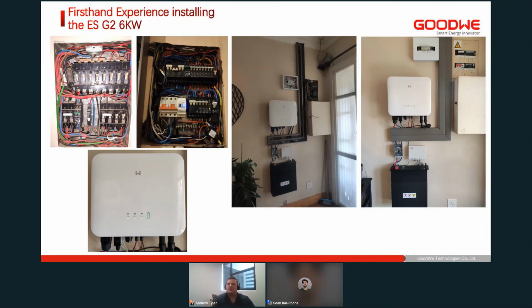And then on the right, we've just got an overall picture. You'll see that you've got your BMS above the battery. You've got your DC battery breaker or protection, as well as conduits. And you've got two separate conduits, one for AC and one for DC, which is a requirement in South Africa for installing a system. But really a neat installation overall.